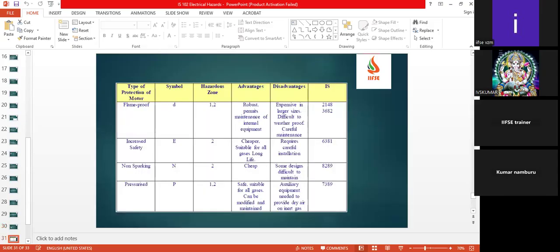Okay, if you see the flame proof, which is D, it can be used in zone 1 and 2. So the advantages will be robust, permits maintenance of internal equipment, and the disadvantages will be expensive in large sizes, difficulty to weather proof, careful maintenance. And we can see more detail in IS 2148 as well as 3682.